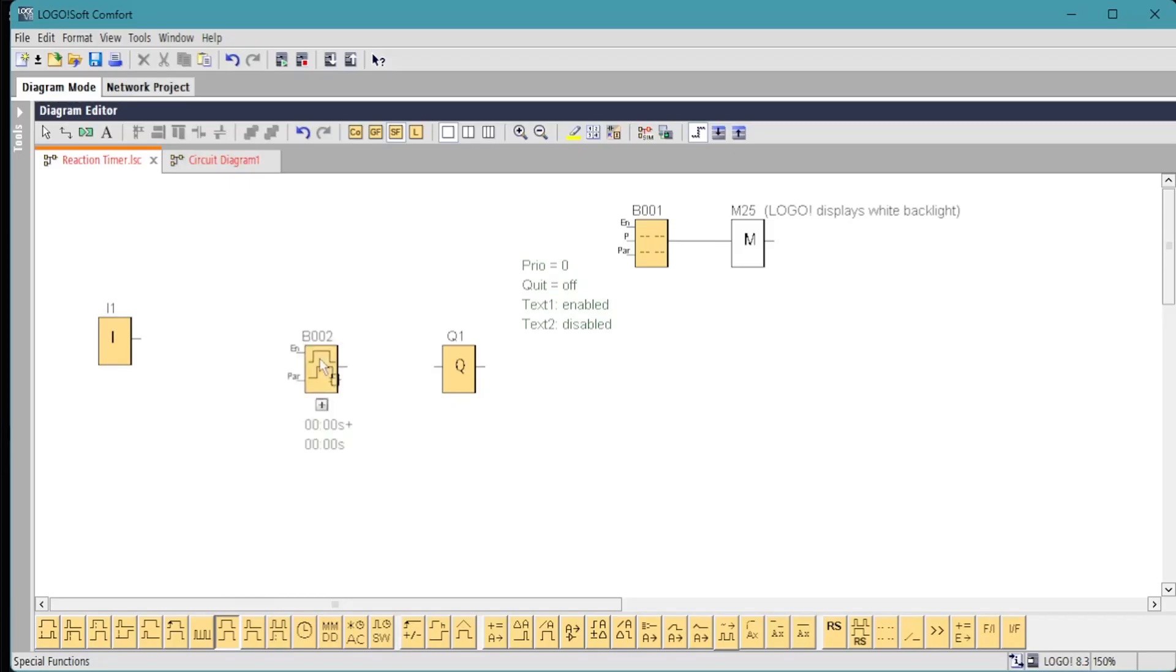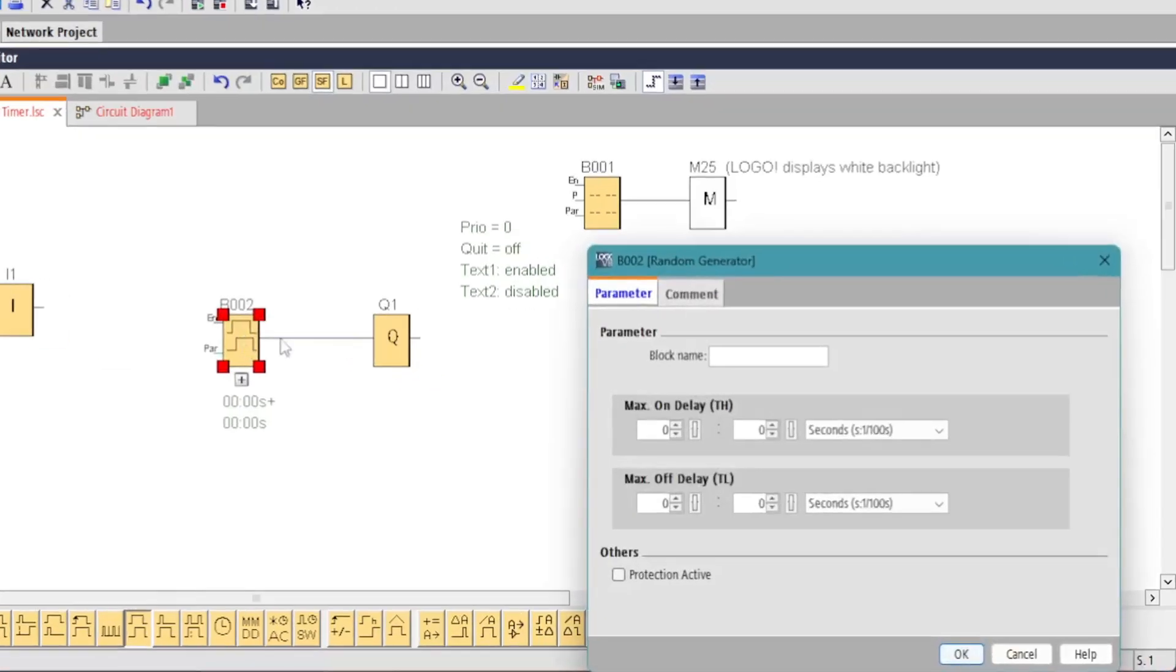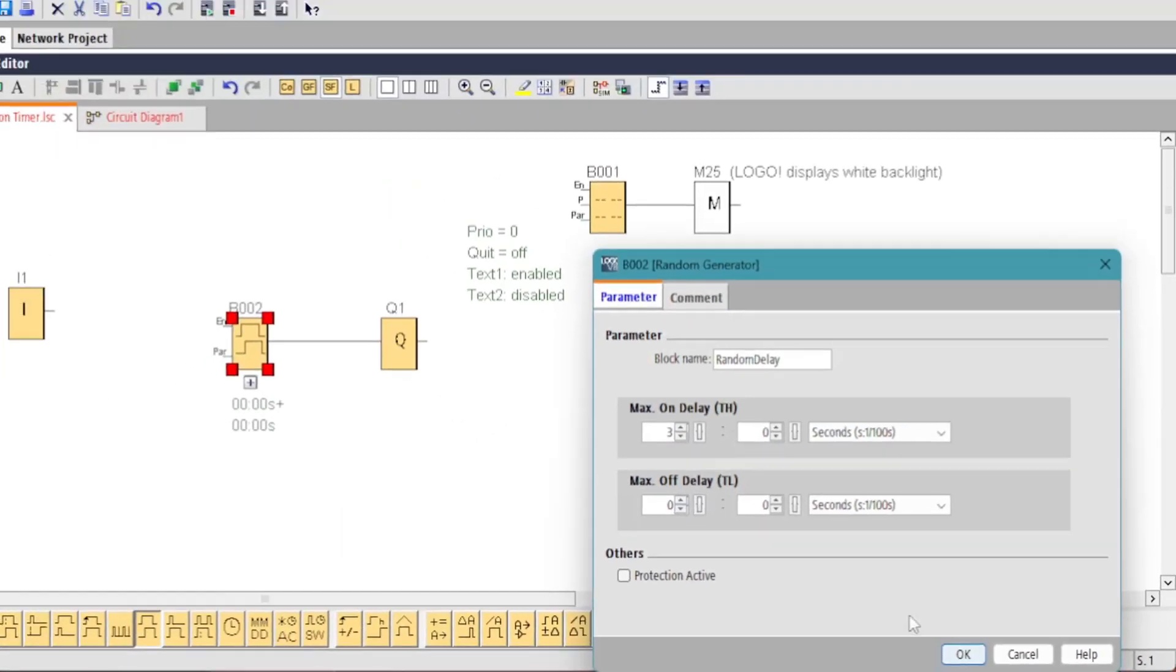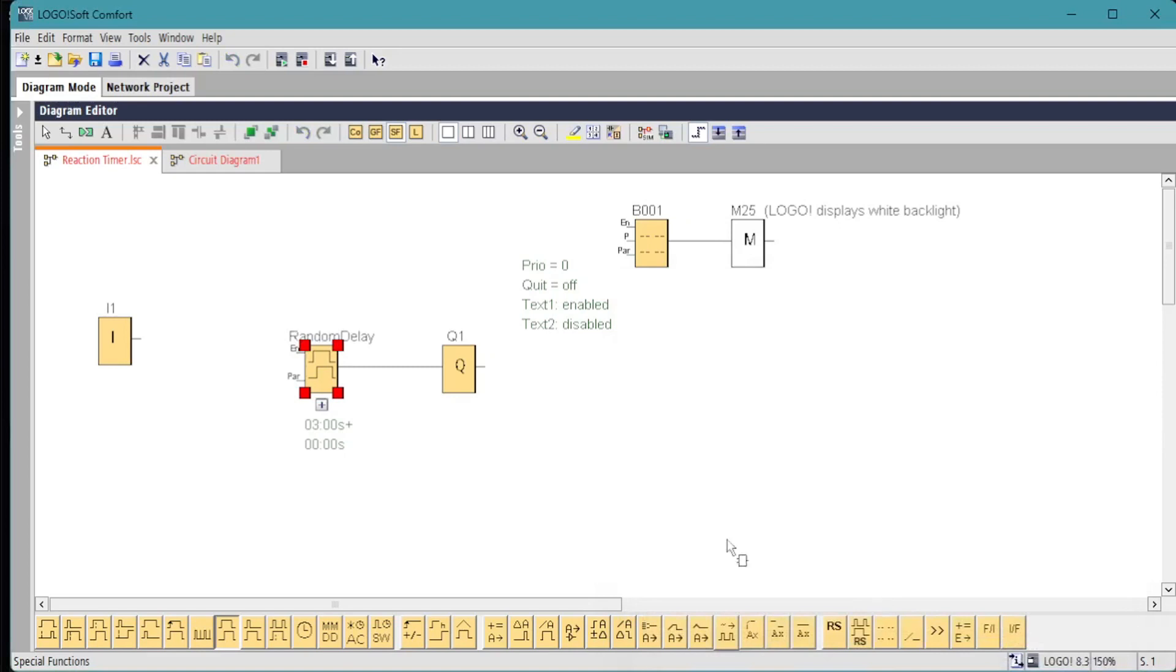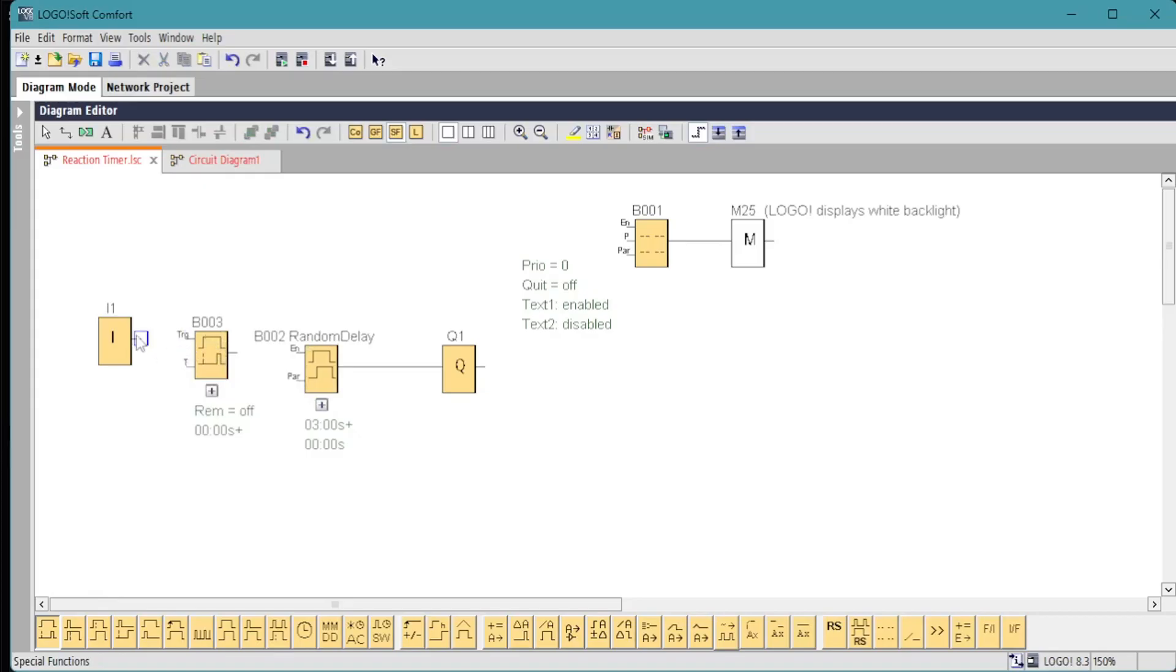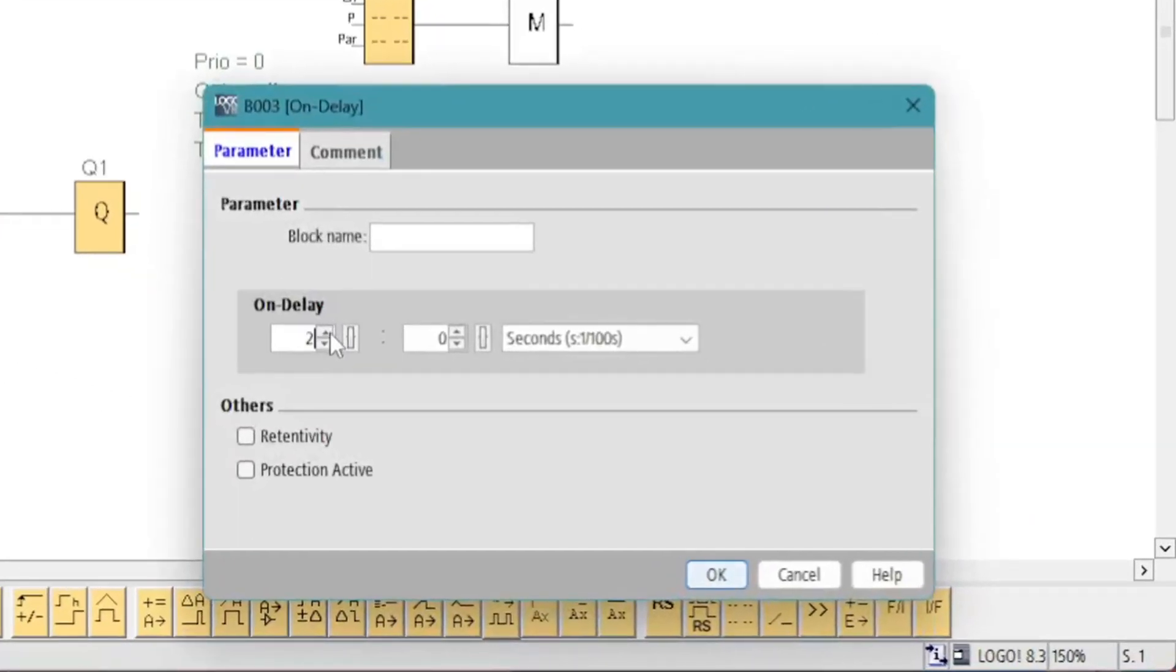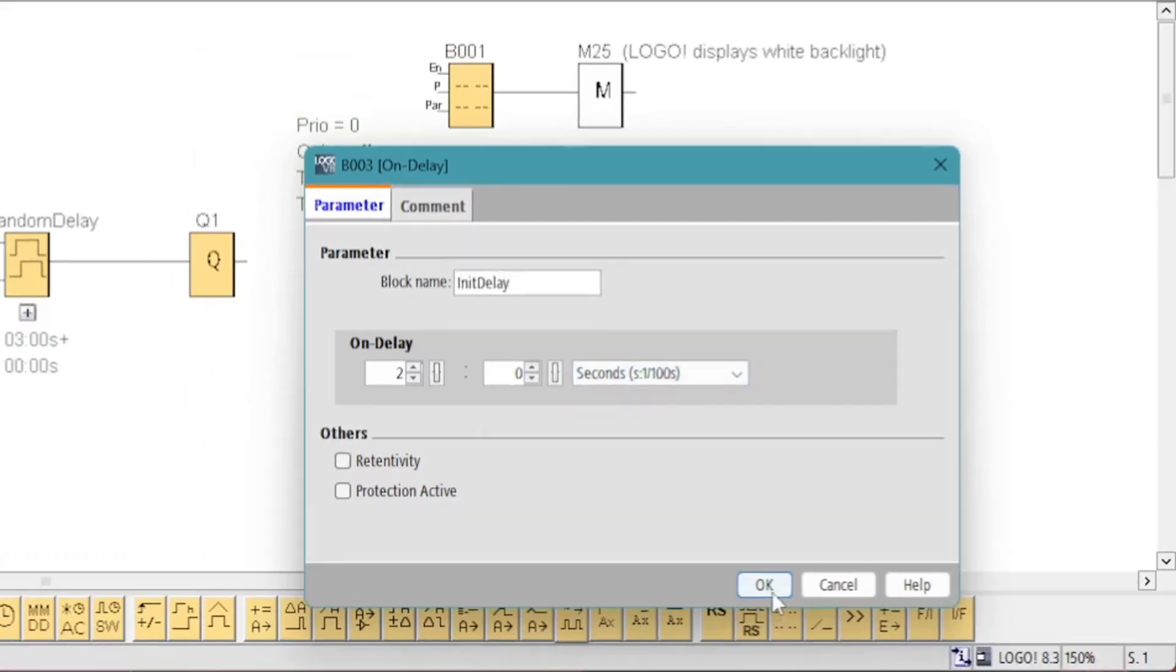From the special functions we select the random timer. We want between two and five seconds, but we notice that we can't set an initial delay on this, so we set it for three, the difference between the minimum and maximum time. We'll add in an on delay timer in front of that to delay the initial two seconds. So the two seconds plus the maximum of three from the random delay should give us a delay between two and five seconds.